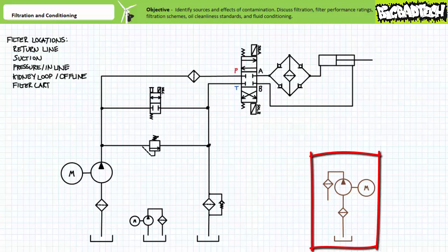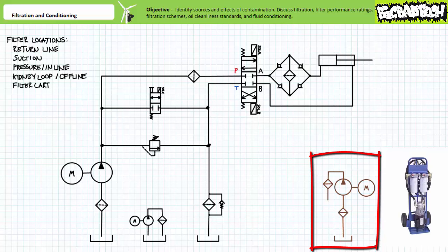Finally, filtration can occur external to a system with the use of something called a filter cart. A filter cart or portable filtration unit is a special purpose device used to transfer fluid from a storage container to a reservoir, as well as perform thorough filtration that would ordinarily be cost prohibitive if included in a regular system. A filter cart is essentially a portable pump and a filter or filters. A filter cart can be used to fill a new system, empty an old system, change old fluid or filter existing fluid.